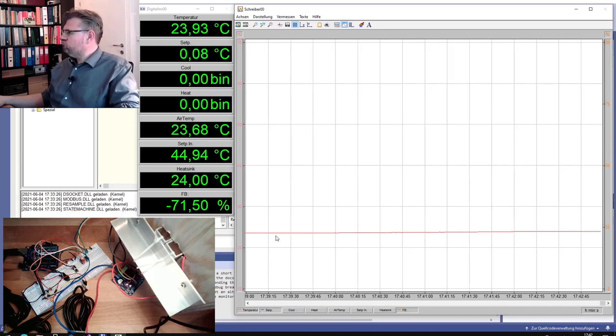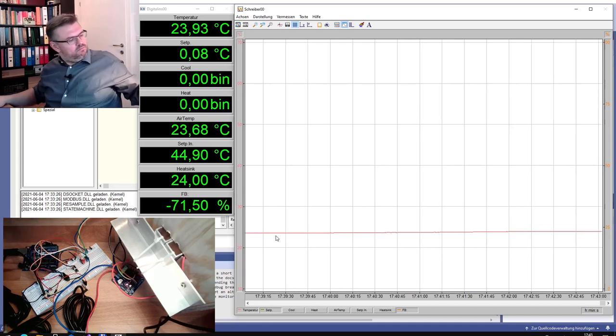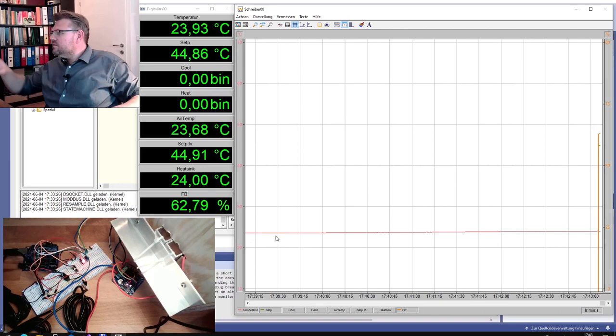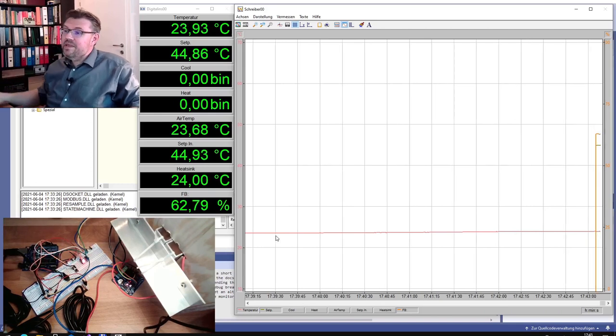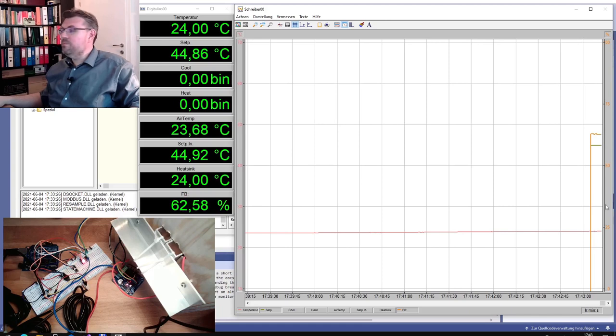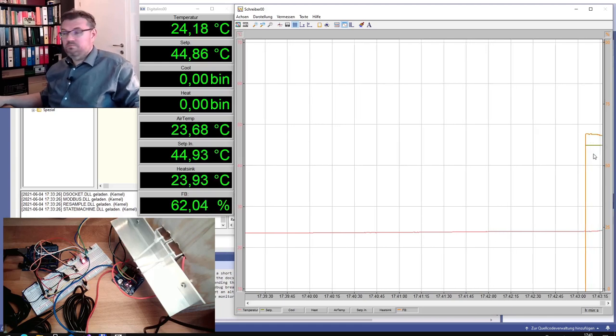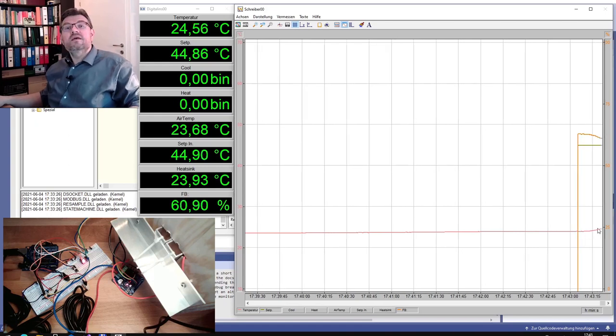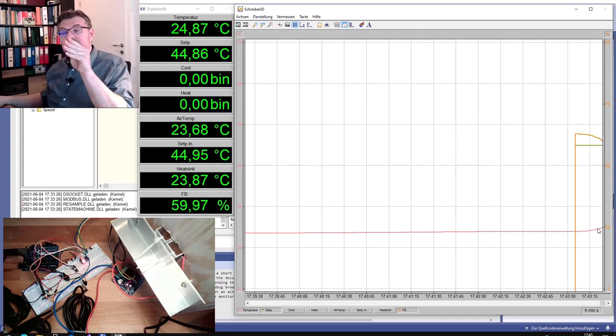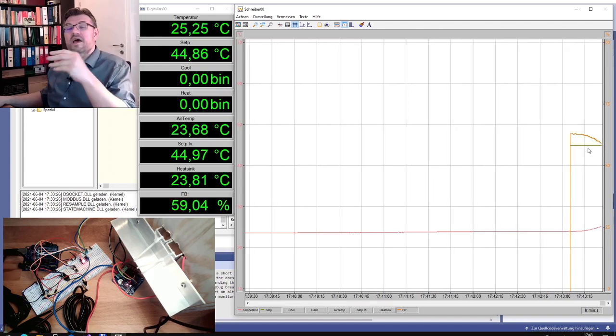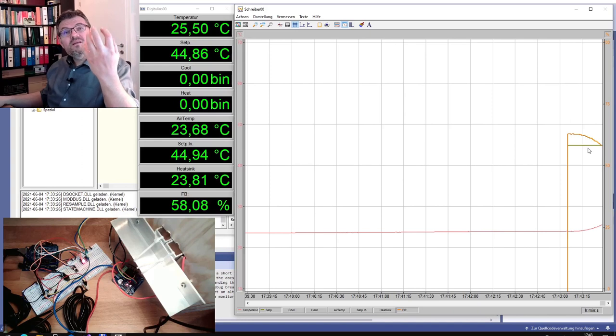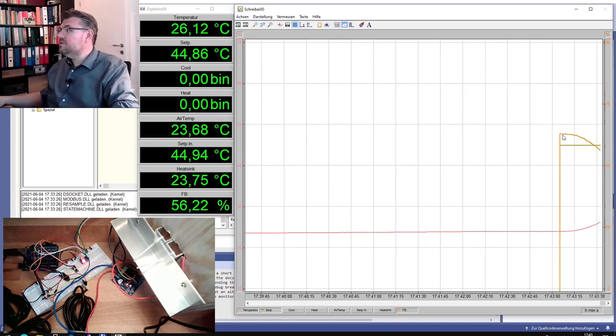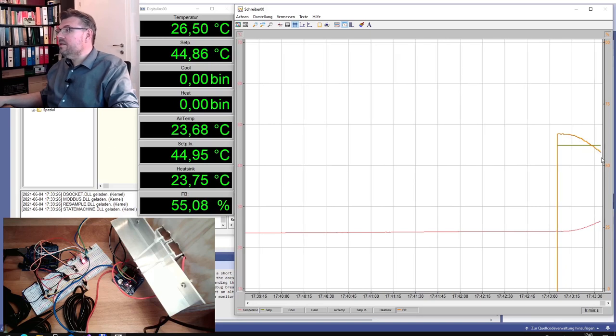So let's simply trigger the set point. The set point is jumping immediately. The correcting variable also jumped to 63 percent. You see, this is what the proportional factor is in place. Now we had a controller difference. Now you see the temperature is getting higher and the controller difference disappears. Also the proportional gain, the gain control difference, is also disappearing. You see it's going down.